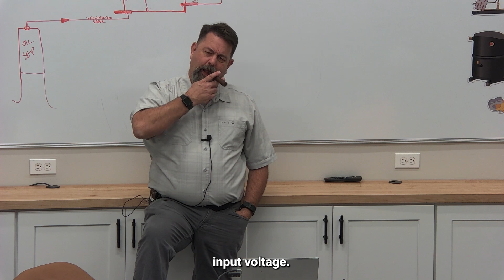How's Novar telling it to overdrive at night then? It's just a digital close, built into Novar's system. We'd be able to put that in place of that switch temporarily, so you could replace your subcooler control, you could replace the EPR, but not the EEV, because it won't adjust to superheat. So even though that's the general one, we're fairly limited in the application - because it doesn't have an input or an output for temperature.